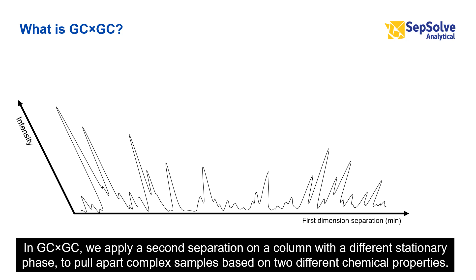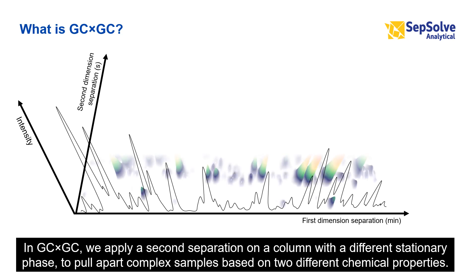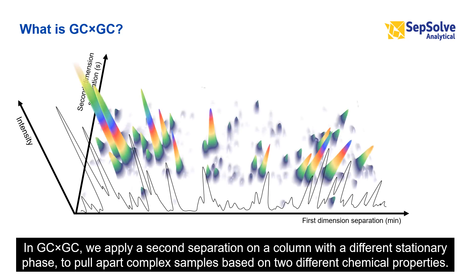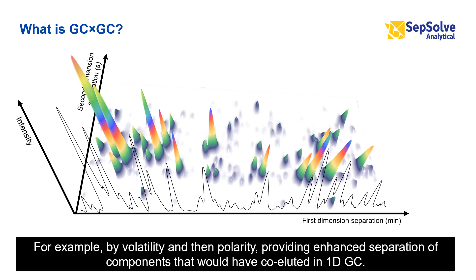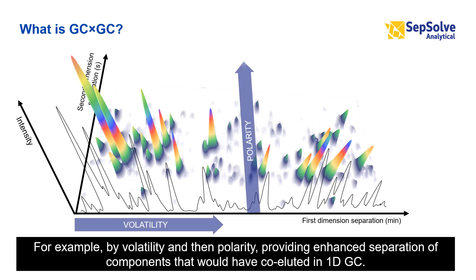In GC×GC, we apply a second separation on a column of a different stationary phase to pull apart complex samples based on two different chemical properties — for example, by volatility and then polarity — providing enhanced separation of components that would have co-eluted in 1D GC.